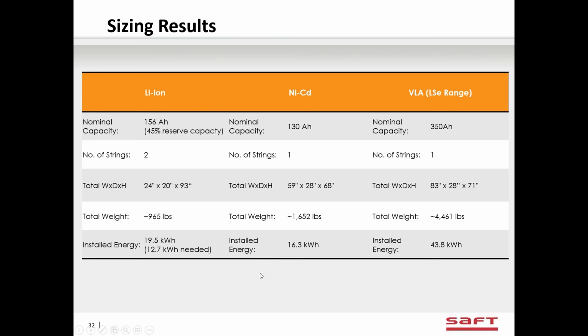This is a comparison chart. Here you can see what I was talking about with the lithium ion versus the lead acid. The lead acid needed 350 amp hours. The lithium ion actually needed about 100 amp hours to do this job, but I have 78 amp hour strings, so I needed 2 of them. So I actually have a 45% reserve capacity with 156 amp hours. If I could choose a smaller increment, I could have met this with a smaller battery, but 156 amp hours, 2 cabinets or 2 strings.